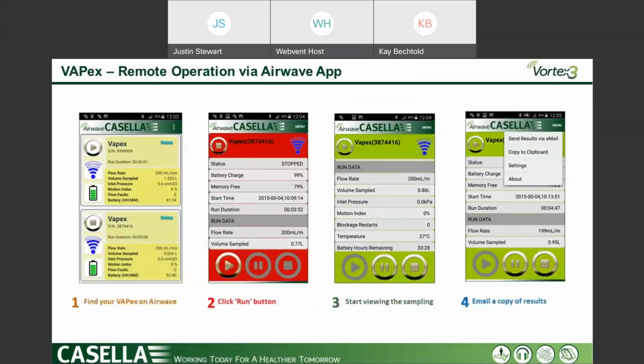This gives you a snapshot window of what Airwave looks like when you do that initial screen grab. You're looking for which serial number, what flow rate, to ensure the flow rate, and how long it's been running. If we experienced any faults, we work on a green, yellow, red system. Green, the pump is running; red, the pump is stopped; and yellow, the pump is paused. Actually, it's blue if the pump is paused, excuse me. It also does the countdown of the pump, where you do the 3, 2, 1, and the pump is engaged. It'll turn from red to green.